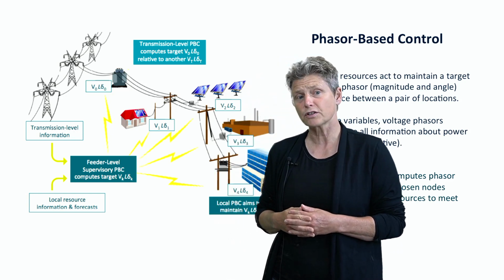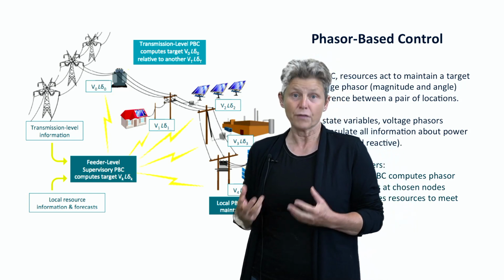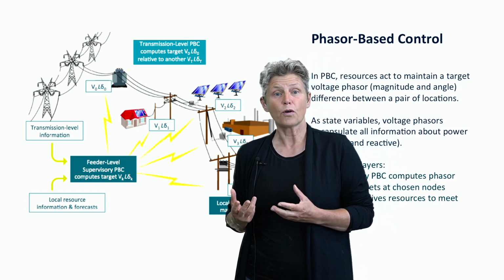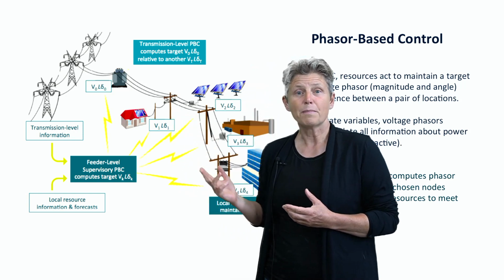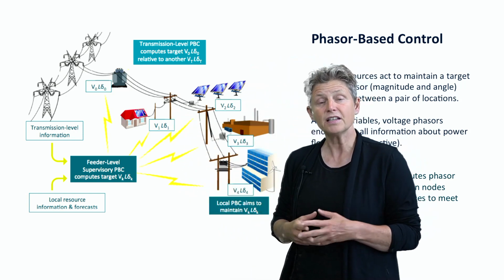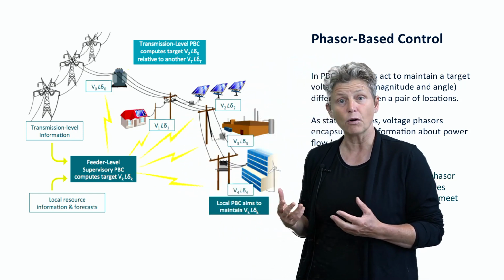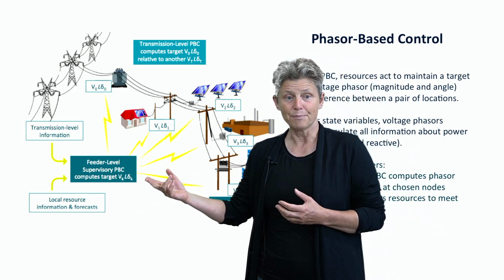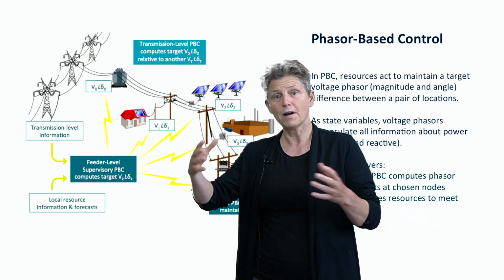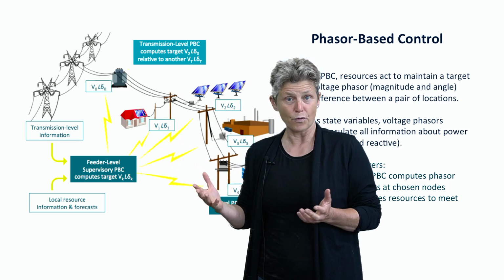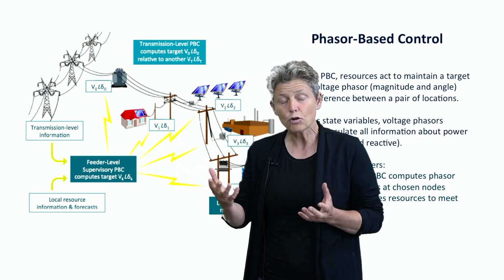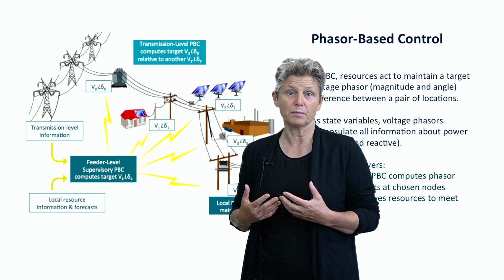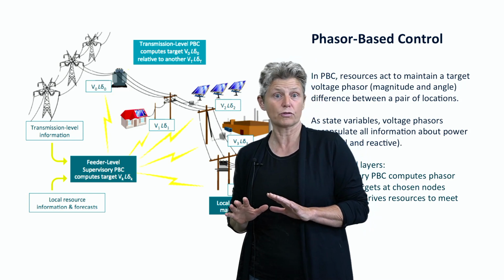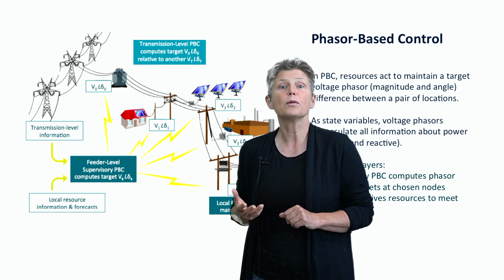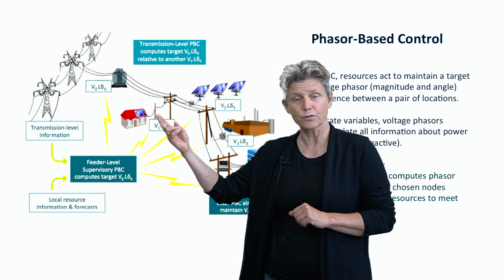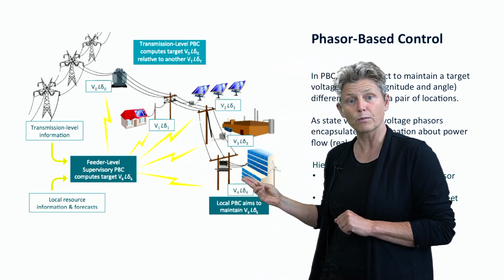In phasor-based control, this is a very precise way to formulate the power flow condition we'd like to see, and the supervisory controller can take all kinds of input information from economics and weather forecasts, incorporate that into an optimization. We're agnostic to the criteria, but it will compute target voltage phasors for every point on the network.